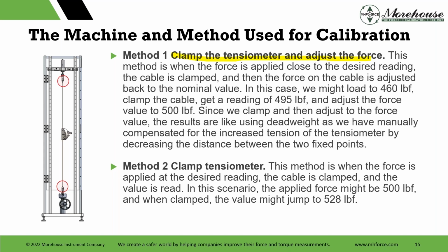I saw these online. There are people talking about the different methods, but I call method one: clamp the tensiometer and adjust the force. So basically what we're doing here is we might say we want to apply 500 pounds of force. We load to 460, clamp the cable tensiometer, get a reading of 495, and then we just turn the wheel counterclockwise till our load cell reads 500.00 pounds. And then since we clamp and adjust the force value, the results are likely the same as using dead weight.